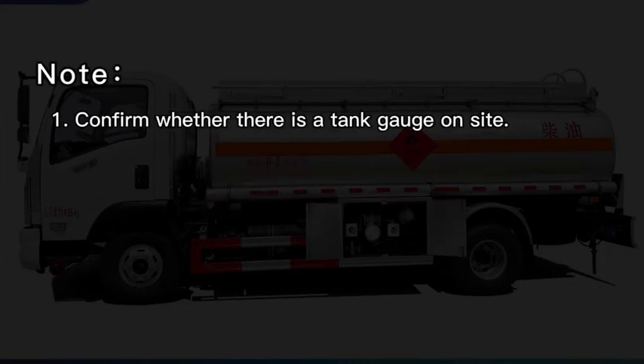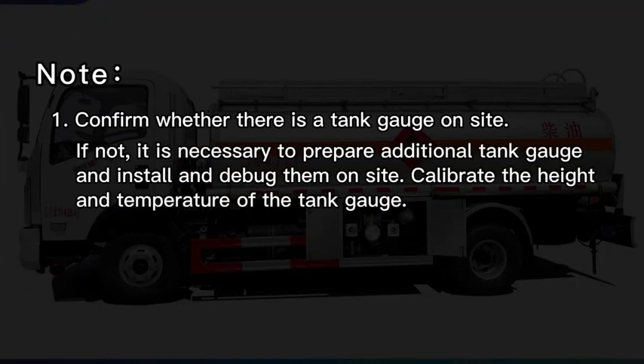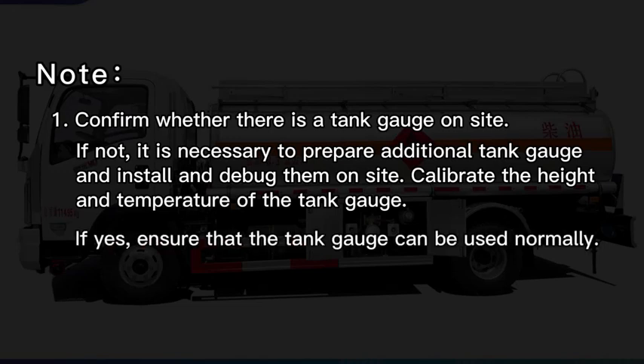Note 1. Confirm whether there is a tank gauge on site. If not, it is necessary to prepare an additional tank gauge and install and debug it on site. Calibrate the height and temperature of the tank gauge. If yes, ensure that the tank gauge can be used normally.